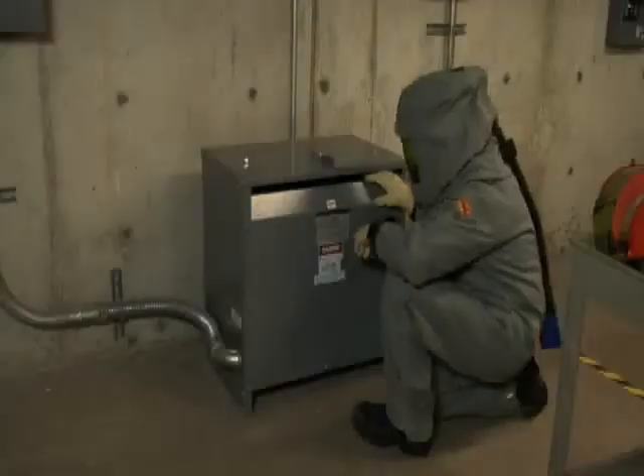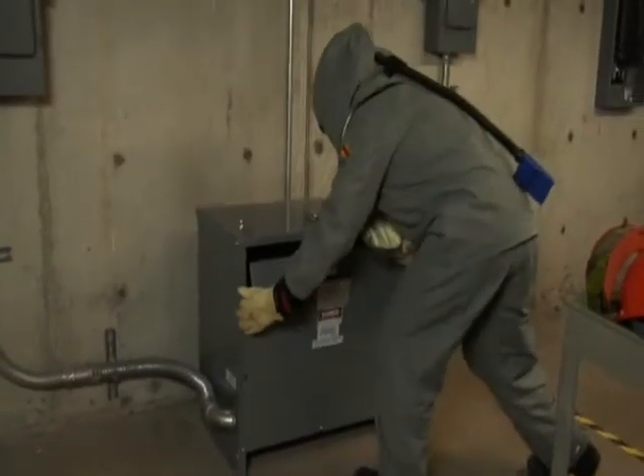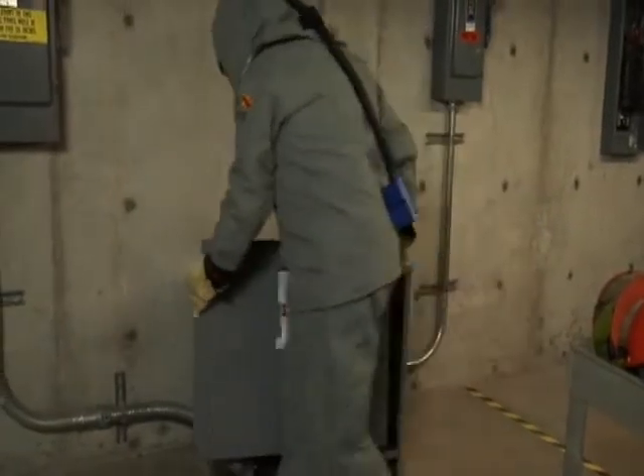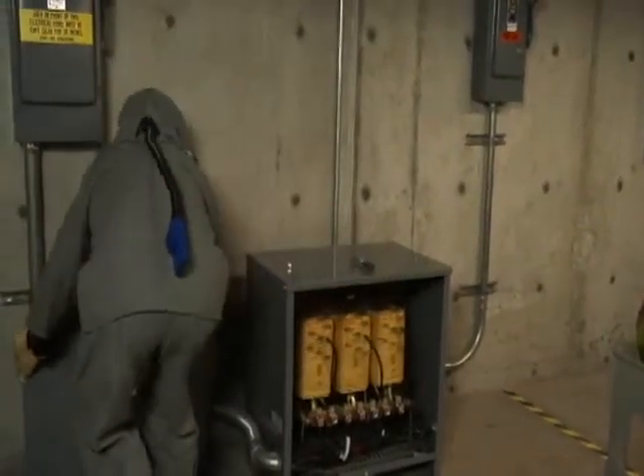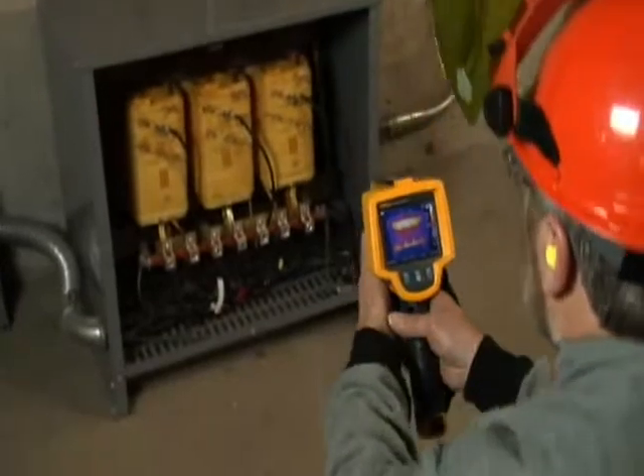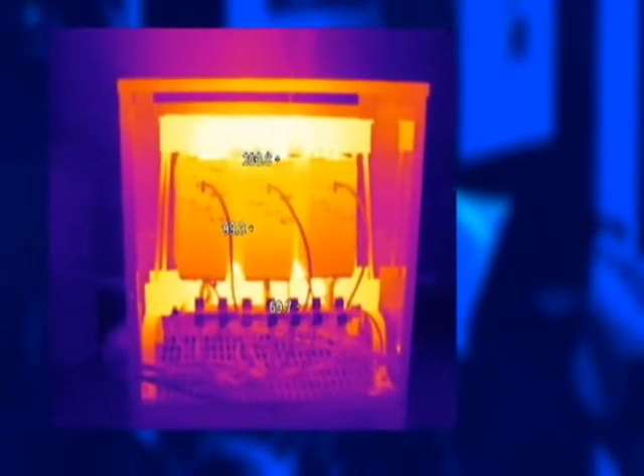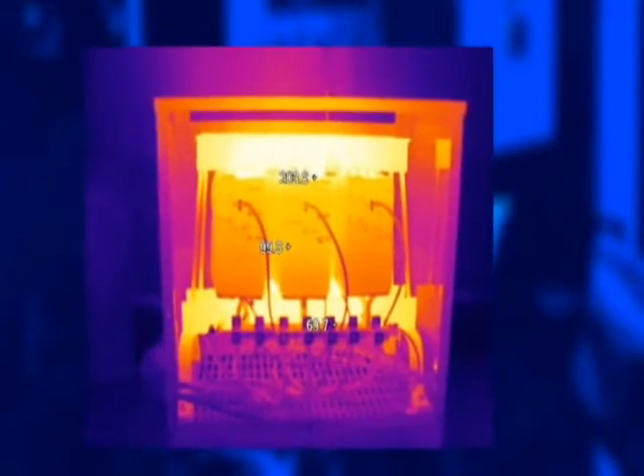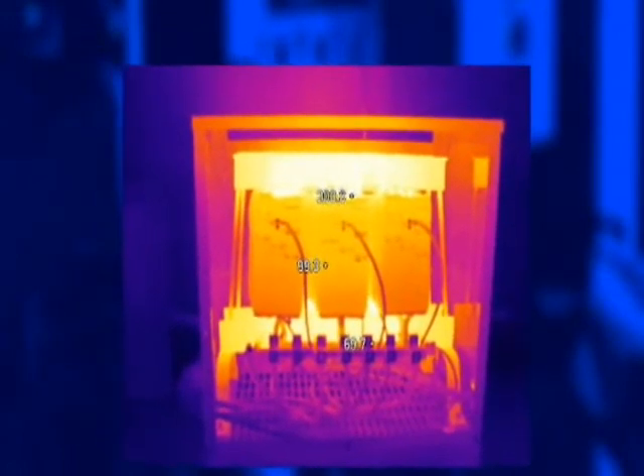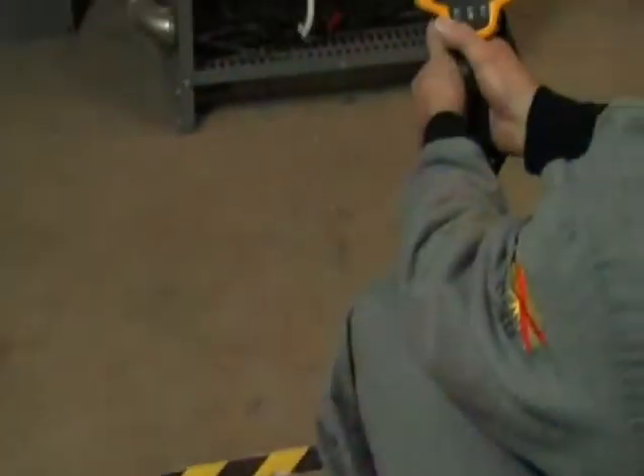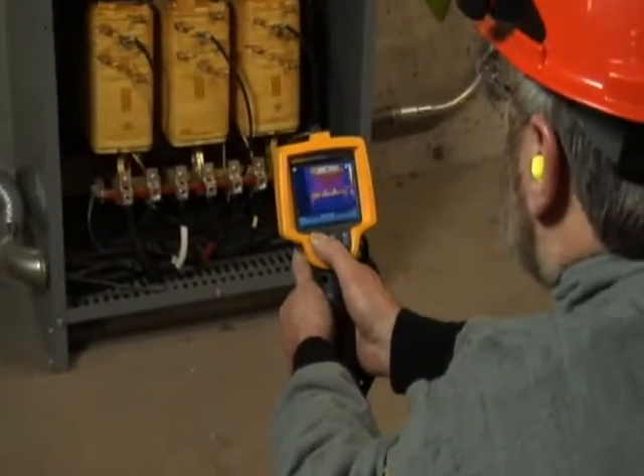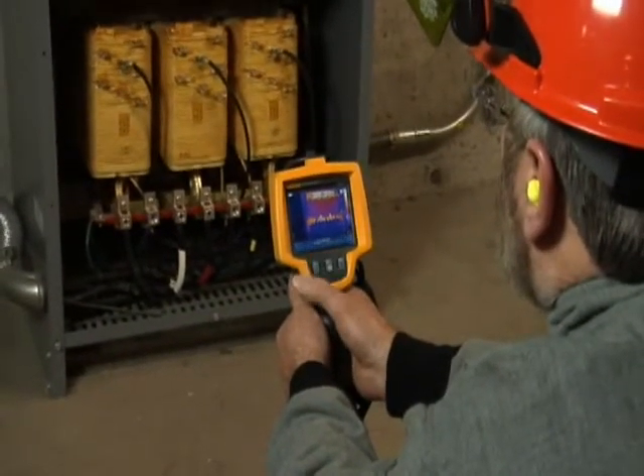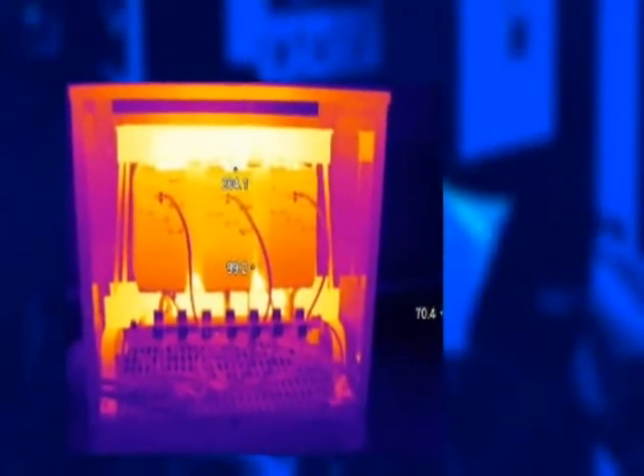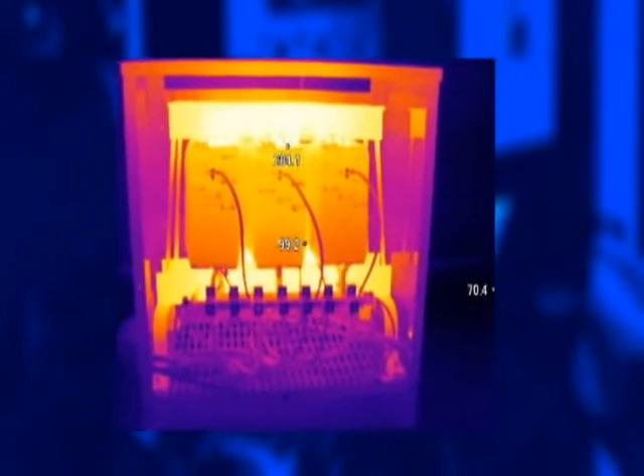You should scan the transformer with either a thermal imager or an infrared thermometer. That requires taking off the cover. Determine the hazard risk category for the job, either from the arc flash label or, if not present, from the tables in NFPA 70E. Compare the temperatures of similar components, such as terminations and coils, to one another. A higher temperature on one phase may indicate unbalance. A higher temperature on the neutral termination may indicate the presence of harmonics.